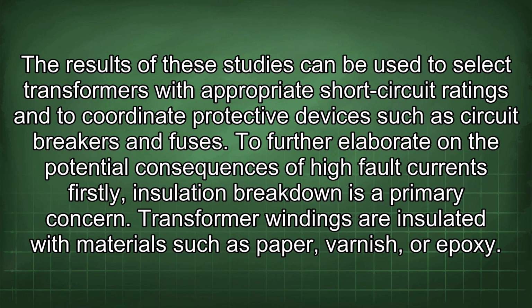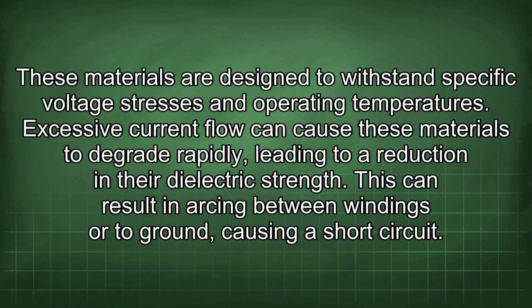To further elaborate on the potential consequences of high fault currents, firstly, insulation breakdown is a primary concern. Transformer windings are insulated with materials such as paper, varnish, or epoxy. These materials are designed to withstand specific voltage stresses and operating temperatures. Excessive current flow can cause these materials to degrade rapidly, leading to a reduction in their dielectric strength. This can result in arcing between windings or to ground, causing a short circuit.